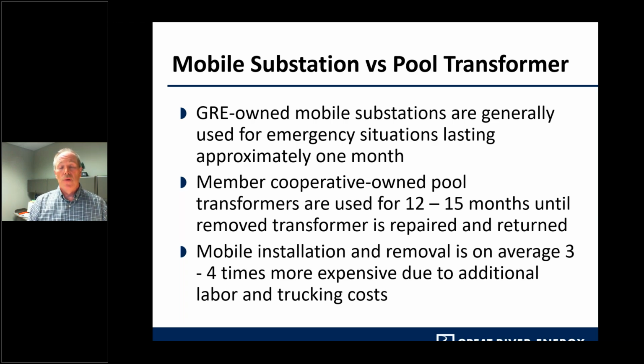The 3 GRE-owned mobile substations we have are used mostly for emergency situations, lasting less than a month. But if the situation arises where the mobile sub is needed for a longer duration, say up to a year, GRE will then look at installing what we call a pool transformer, which is just a network of transformers owned by the members. That way, when we install a pool transformer, the mobile can be available for other emergency needs.